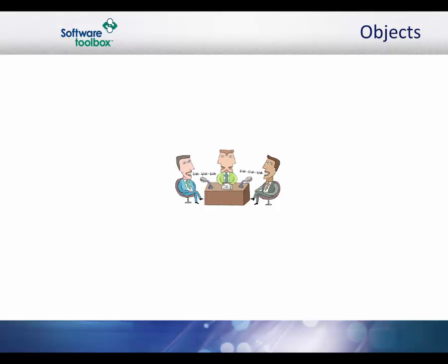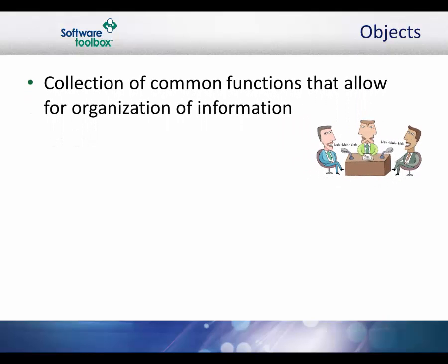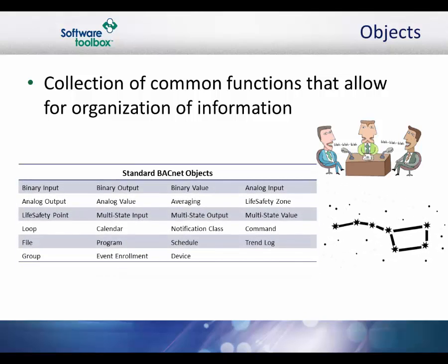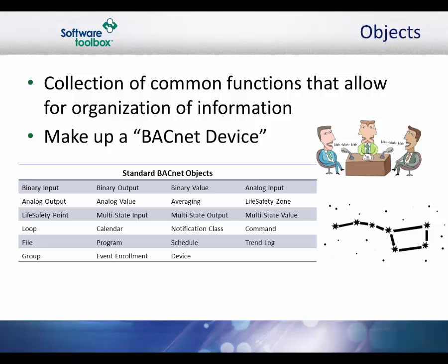Examples are analog and binary inputs and outputs, schedules, control loops, and alarms. This standardized model of a device represents these common functions as collections of related information called objects, each of which has a set of properties that further describe it. This concept allows for organization of information relating to physical inputs and outputs as well as non-physical concepts like software or calculations. Objects may represent single points or logical groupings of points that perform a specific function. Most experts indicate there are 23 standard BACnet objects used in building automation systems. A BACnet device is simply a collection of objects that represents the functions actually present in a given real device.